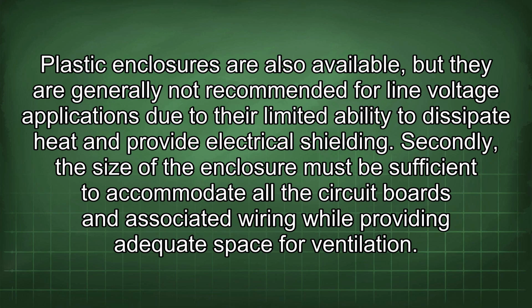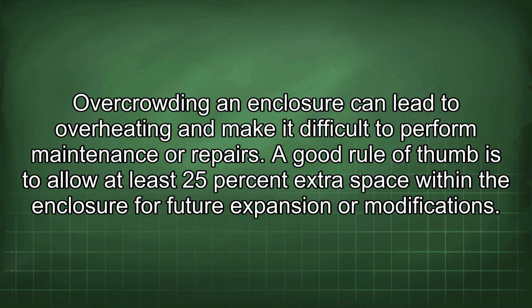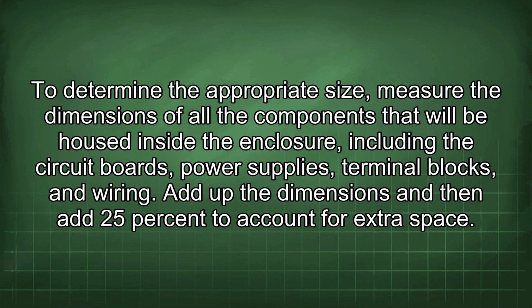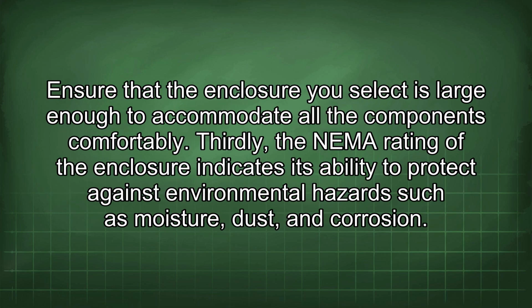Secondly, the size of the enclosure must be sufficient to accommodate all the circuit boards and associated wiring while providing adequate space for ventilation. Overcrowding an enclosure can lead to overheating and make it difficult to perform maintenance or repairs. A good rule of thumb is to allow at least 25% extra space within the enclosure for future expansion or modifications. To determine the appropriate size, measure the dimensions of all the components that will be housed inside the enclosure, including the circuit boards, power supplies, terminal blocks, and wiring. Add up the dimensions and then add 25% to account for extra space. Ensure that the enclosure you select is large enough to accommodate all the components comfortably.